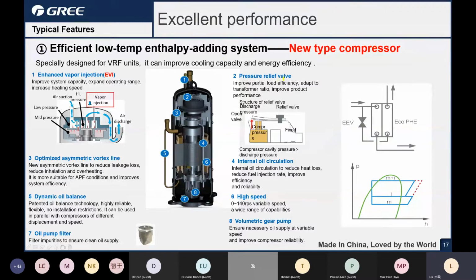And the second one is the pressure relief valve. This relief valve is the built-in pressure relief valve in the compressor here. So if the load is partial load, this relief valve will be opened automatically to improve the refrigerant circulation and make sure it can satisfy the unit's output. Okay, that's the second one.